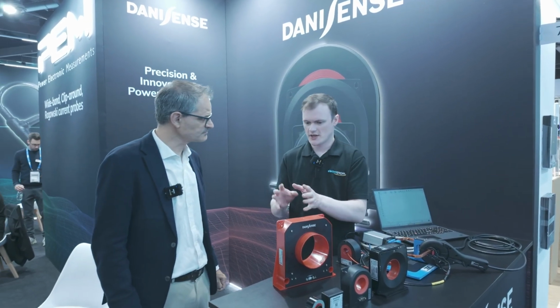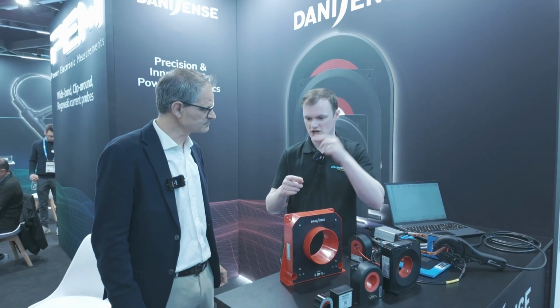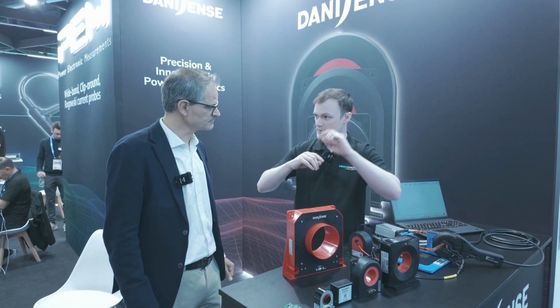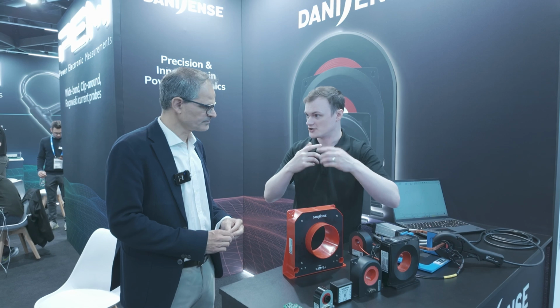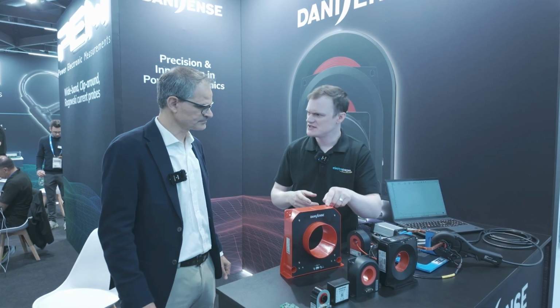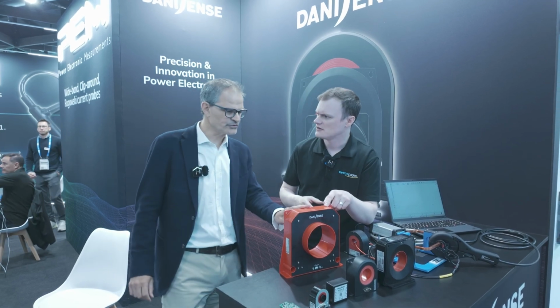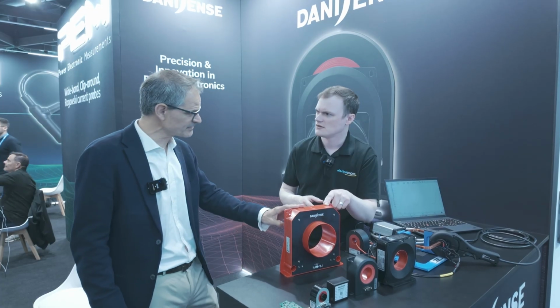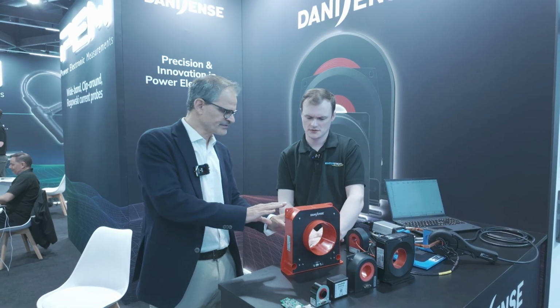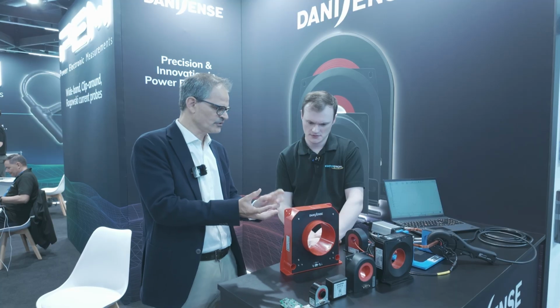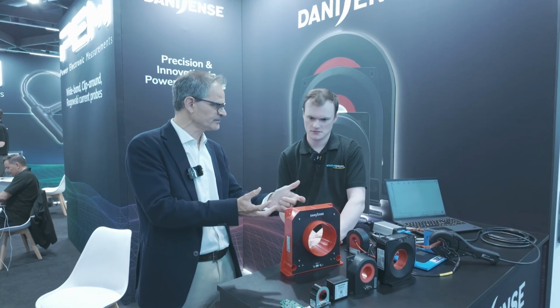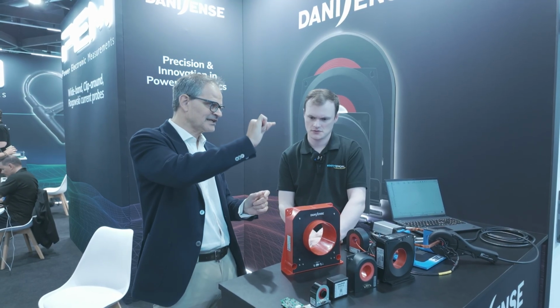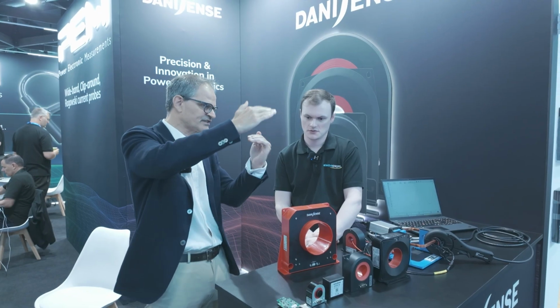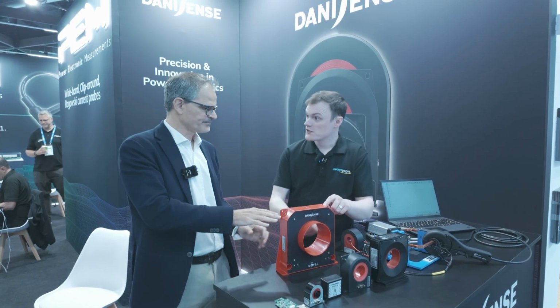That's interesting, because I know with transformers you need AC to change the magnetic field so you can measure the output changes for the current. So how do you do it for DC? This is a technology called fluxgate. The principle is pretty easy. You have the magnetic core, you saturate and desaturate it, and then you get a very clean, symmetrical signal. So you drive the coil.